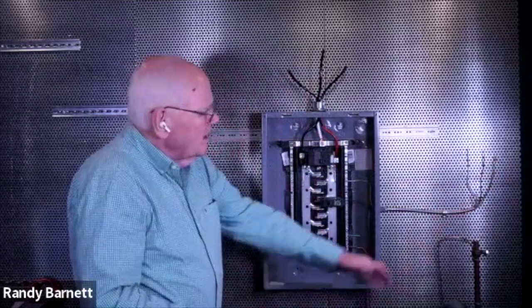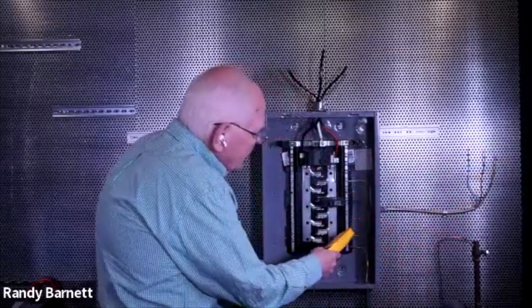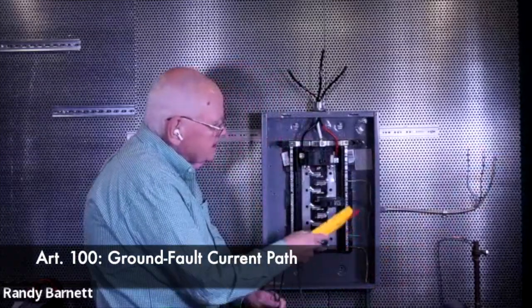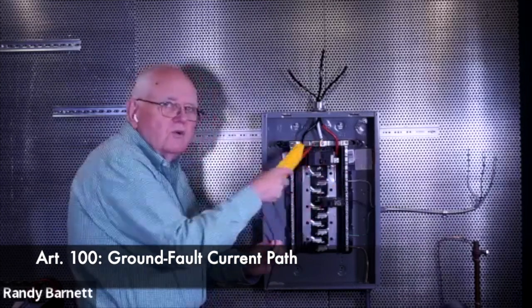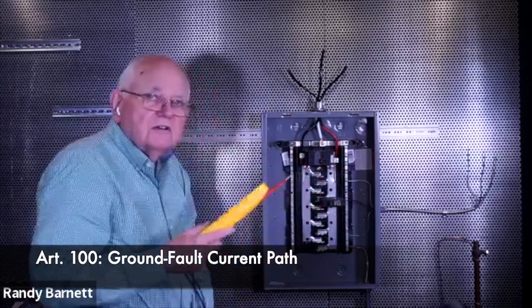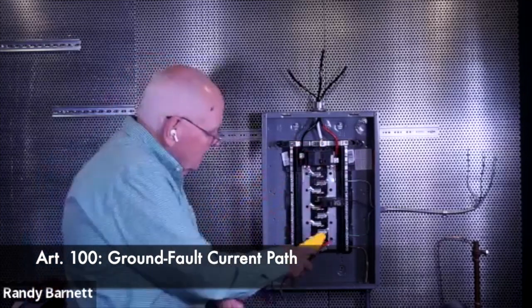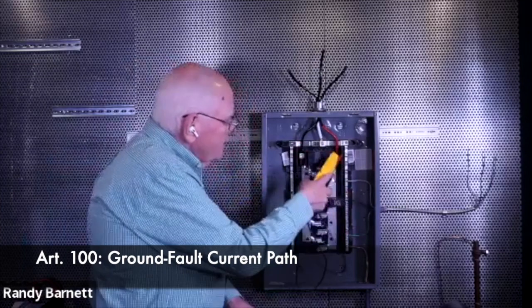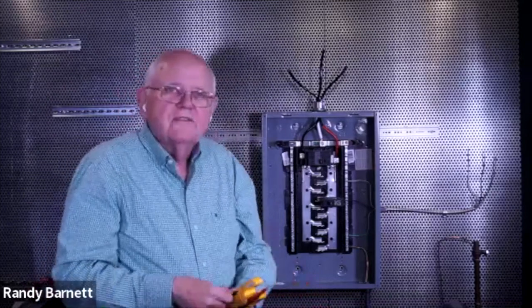Why? Well, think about it. If current flows into the metal frame of my equipment out here, it wants to get back to the source. That's where I'd like it to go. I don't want to touch the metal frame of that equipment and have that current flow through my body and back to the source, that's for sure. Okay? So we'll take it through the equipment grounding conductor, and the current will flow back in the equipment grounding conductor to that same grounded bus bar that's attached to the neutral wire coming off of our service. And the current's trying to get back to the transformer. So where can it go? It can come in on the grounding bus bar from the green wire, go right on back to the service where it's happy again. It goes back to the transformer, complete path of current flow.